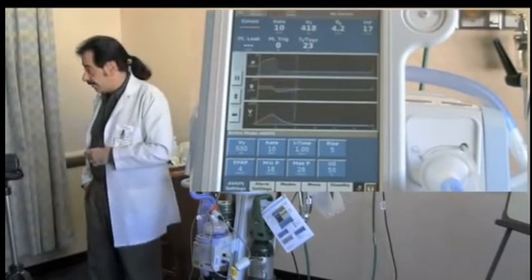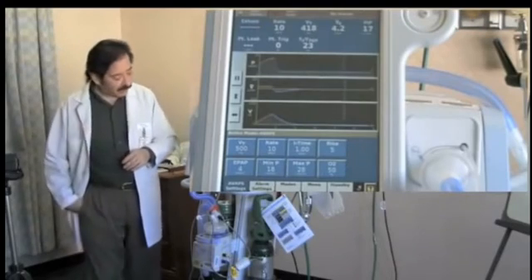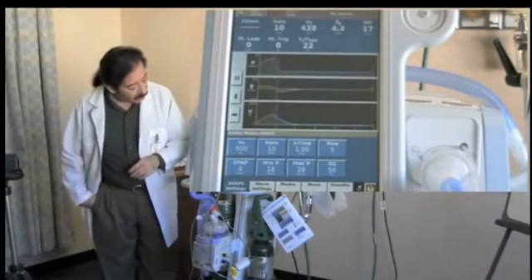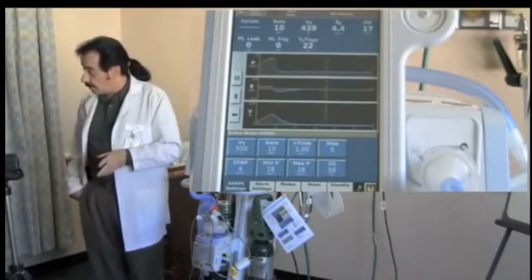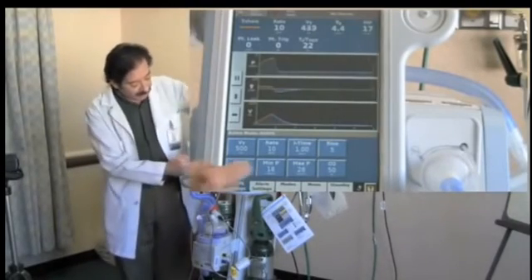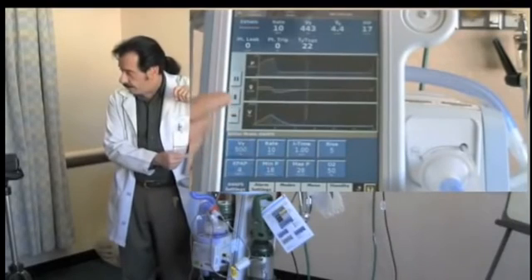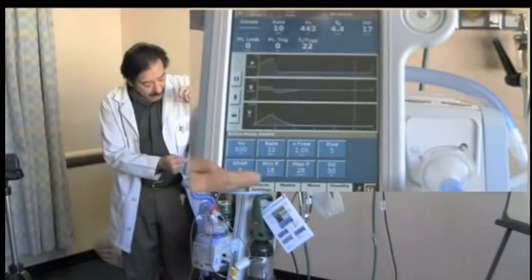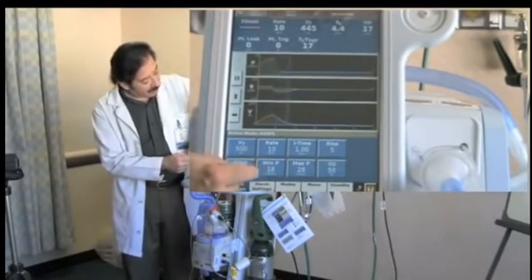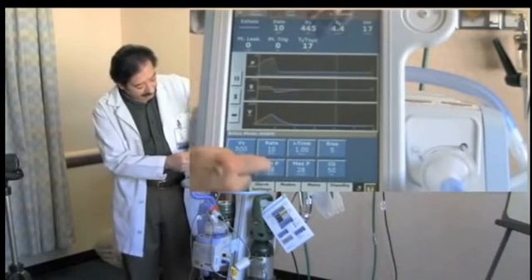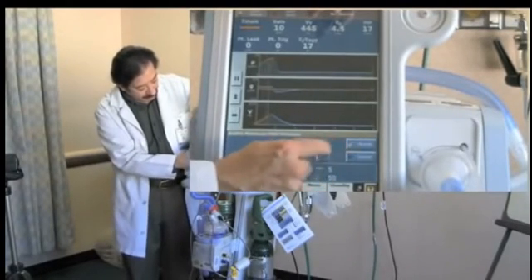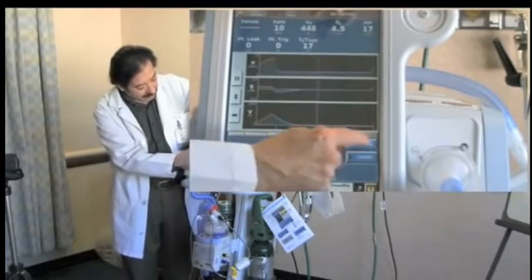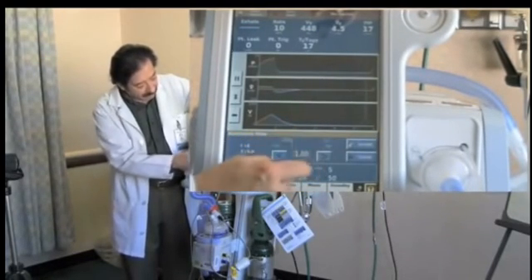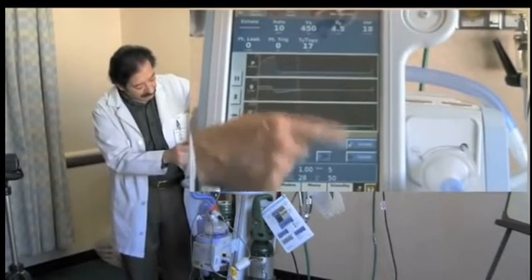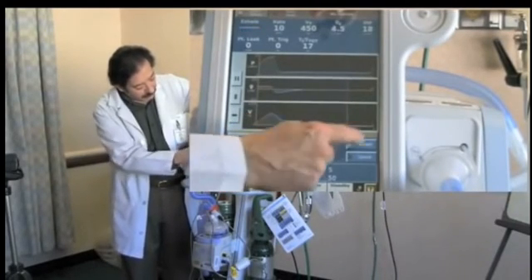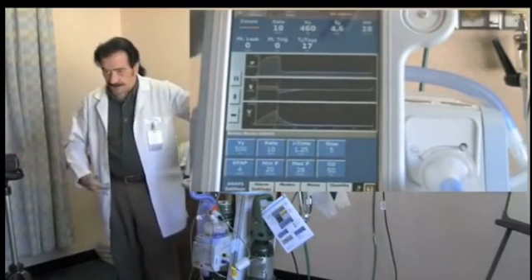So it's going to take me a while to get there, and the doctor may say, no, this is taking too long. So there are some things that we can adjust to more quickly affect the volume that the patient's achieving. One of those is called the P-min. This is the starting point for the pressure support level in the AVAPS mode, okay? So if I'm not getting where I need to be at what it is set at min, I can increase that. So we'll go up to 20, let's say, here. And I can increase the I time, since I spend more time in the area under the curve of the pressure waveform, and so that will increase the volume that's achieved on each breath.